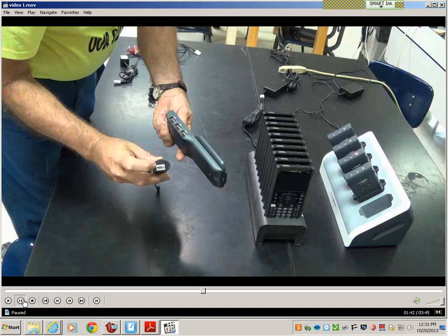But if I was doing a lab where I wanted to have maybe a current probe and a voltage probe at the same time, and I wanted them both on the same handheld, then the lab cradle allows you to do multiple probes. I'm going to demonstrate that in a minute. So the advantage of the lab cradle is that you can do multiple probes. The disadvantage of it is it's another piece of equipment you got to work with.